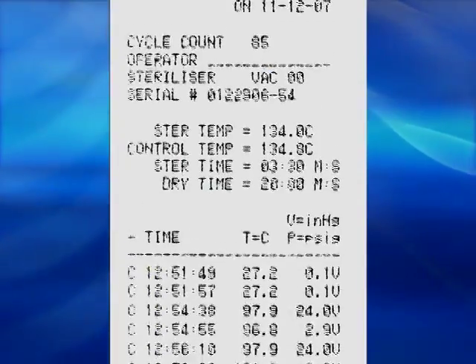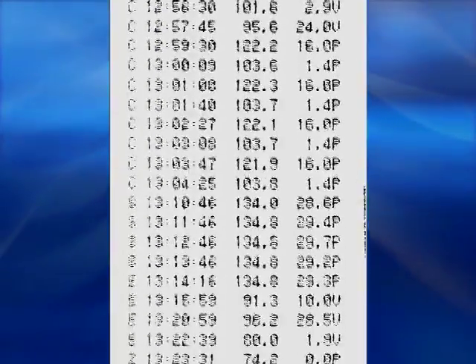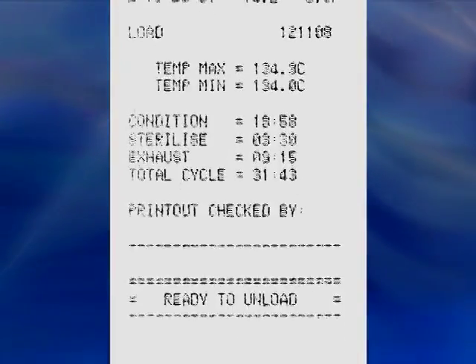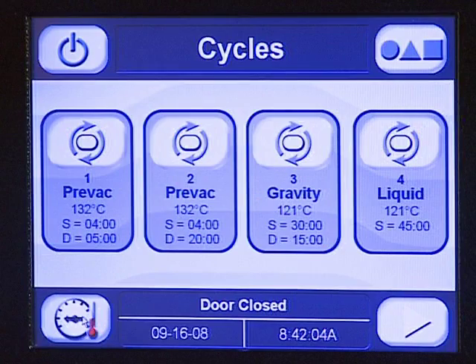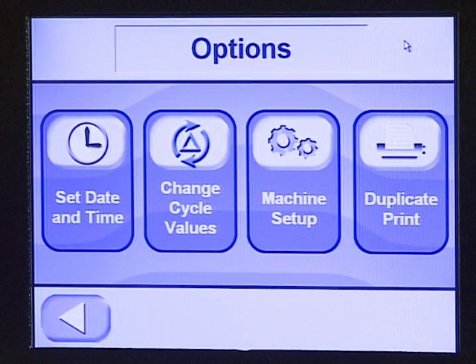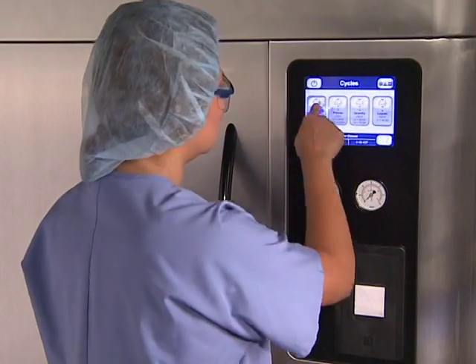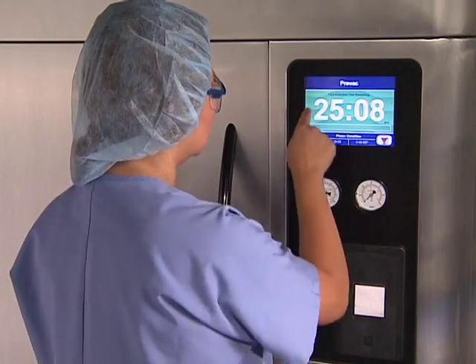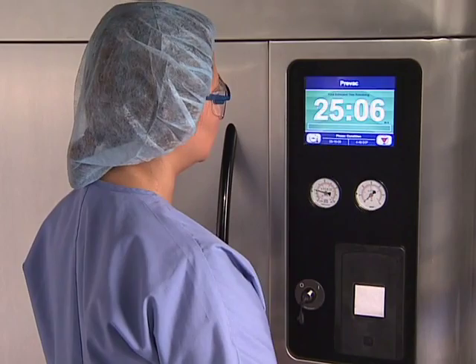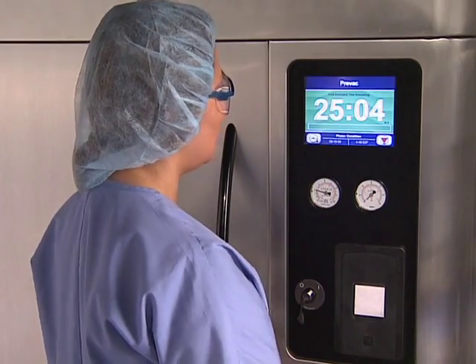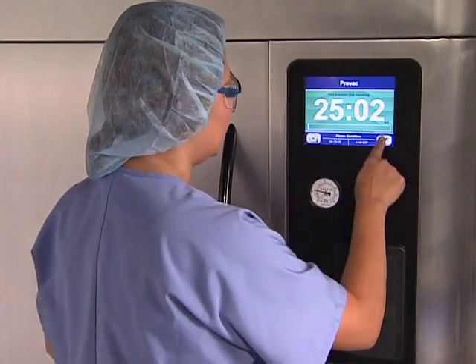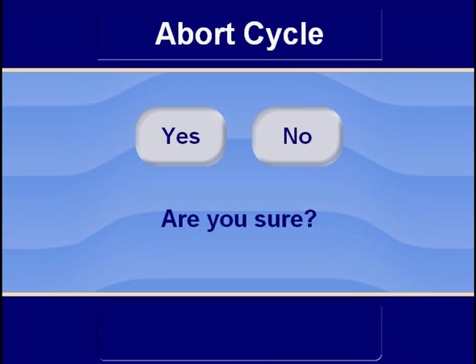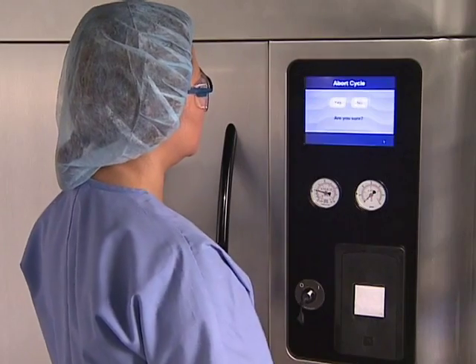The sterilizer documents all phases as they occur throughout the cycle on the printout, including all cycle parameters. To print a duplicate printout of the cycle, press the Options button. Then press the Duplicate Print button. If you discover that you've selected the wrong cycle, or if the sterilizer begins to function incorrectly, you can end the cycle immediately by pressing the Abort button. A prompt screen will ask for confirmation. Press No to cancel the abort and return to the cycle. Press Yes to initiate the abort sequence.